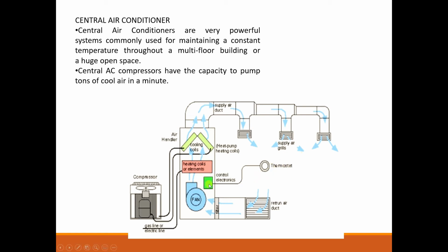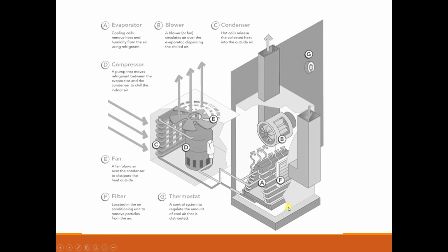This thermostat is always attached over here. I am telling you, in the previous topic we have seen where we have to place the sensors. You cannot simply place the sensor over here, because whatever air is coming here is always cooled. We should know what the output temperature is. According to that only we have to make the changes in the input. For that only this sensor is placed nearer to the output, not in front of the fan, on the side of the output. This is written at the duct. Okay, so these are all the other symbolic diagrams.